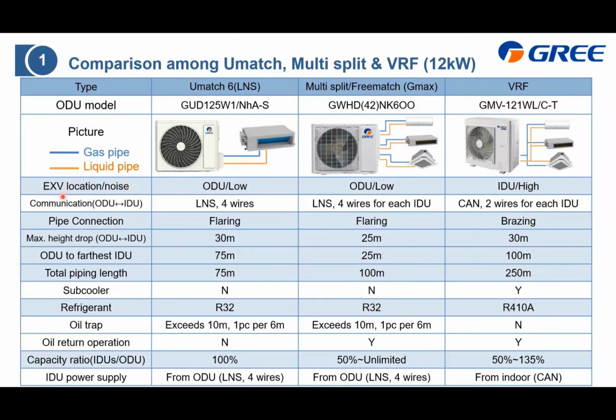First is the metering device. As all these three apply the EXV. So the location, for the Umatch and the multi-split, locates at the outdoor unit, and VRF locates at the indoor unit. And for this reason, for the customer, the noise will be lower for these two and a little bit higher for this one.